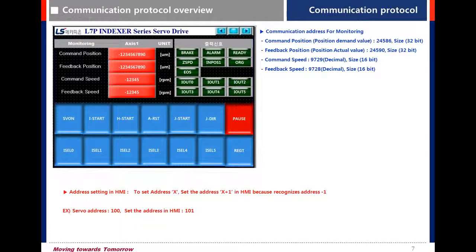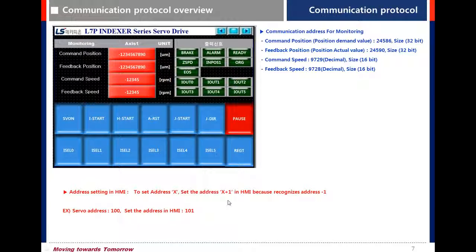To connect with an HMI using Modbus RTU protocol — this is an HMI from LSIS — you can see command position and feedback position. The command position address is shown here in decimal. You need to refer to the address and size in the manual. For address setting in HMI, to set address A, set address A plus 1 in the HMI, because the HMI recognizes address minus 1.